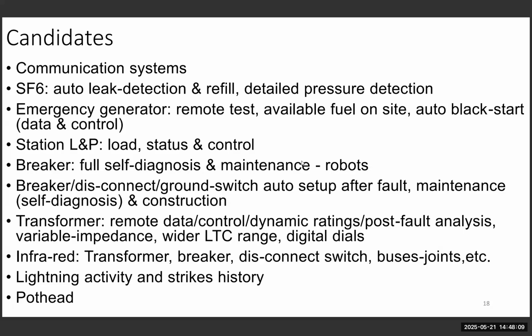It's up to you to think whether this should be the number one reason or not. I mentioned that we were in the business of getting rid of oil-filled equipment for an environmental reason, so we decided to go the SF6 route. But what's really interesting is that now that a lot of the equipment is SF6, they discovered that SF6 is a greenhouse gas and it's terrible for the environment if it leaks. That means we have very sophisticated SF6 leak detectors, and a lot of the substations are GIS, gas insulated switchgear, or gas insulated substations. That's a very important tool because number one, you have to report all the leaks, and number two, if you're not careful and you have enough leaks, and the pressure drops significantly, the insulation may be at risk.